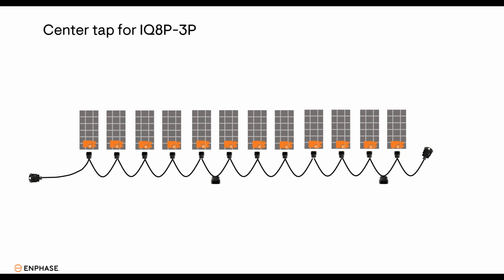But what happens if you didn't start with the very first connector out of the box, or you don't have exactly 12 microinverters in each circuit? To reduce waste, you can start with whatever connector is next in the series. That means at some point you might have two center tap connectors in your circuit. All you need to do is identify which center tap connector has the most microinverters on either side, and that's the one you use to pull your home runs back to the sub panel board. In this example we have two center tap connectors—we'll use the one on the left since it gives us the most microinverters on both sides. Again, this all helps reduce and eliminate voltage rise concerns.